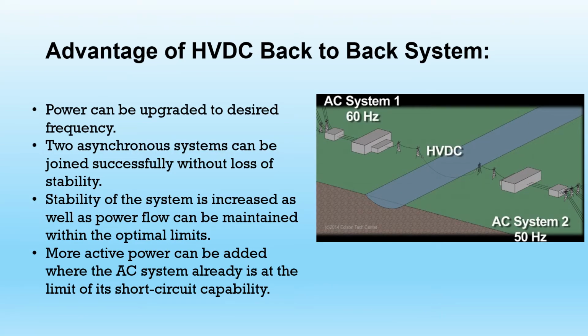HVDC link has many benefits. Some of the benefits are as follows. Power can be upgraded to desired frequency. Two asynchronous systems can be joined successfully without the loss of stability. Stability of the system is increased as well as power flow can be maintained within the optimum limit. More active power can be added where the AC system already is at the limit of its short circuit capability.